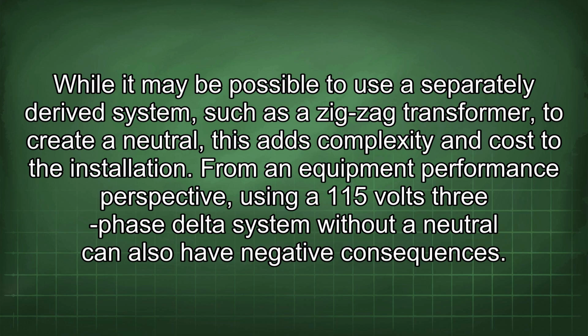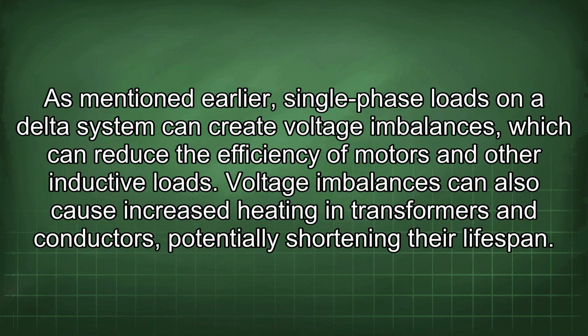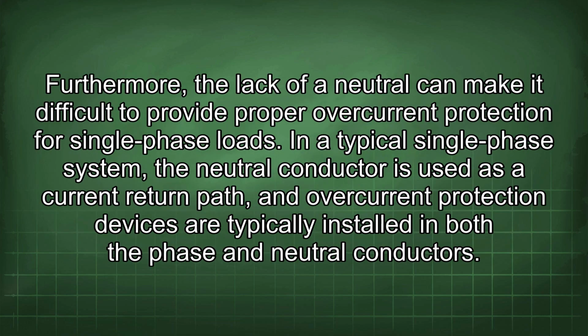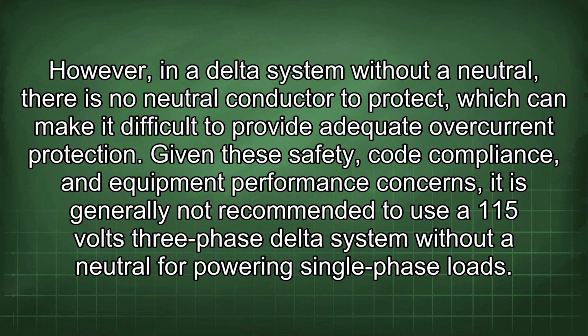From an equipment performance perspective, using a 115 volts three-phase delta system without a neutral can also have negative consequences. As mentioned earlier, single-phase loads on a delta system can create voltage imbalances, which can reduce the efficiency of motors and other inductive loads. Voltage imbalances can also cause increased heating in transformers and conductors, potentially shortening their lifespan. Furthermore, the lack of a neutral can make it difficult to provide proper overcurrent protection for single-phase loads. In a typical single-phase system, the neutral conductor is used as a current return path, and overcurrent protection devices are typically installed in both the phase and neutral conductors. However, in a delta system without a neutral, there is no neutral conductor to protect, which can make it difficult to provide adequate overcurrent protection.